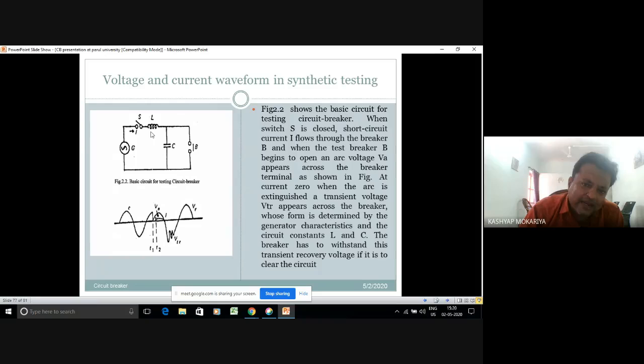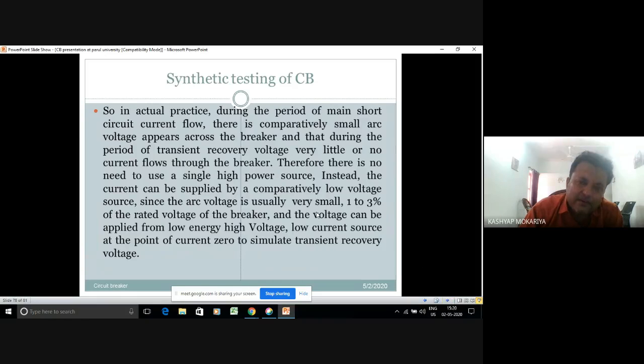Now, this is dealing with the unit level. You can see the difference here. In actual practice, during the period of main short circuit current flow, there is a comparatively small arc voltage across the breaker, and during the period of transient recovery voltage, very little or no current flows through the breaker. Therefore, there is no need to use a single high power source. Instead, the current can be supplied by a comparatively low voltage source, since the arc voltage is usually very small, 1 to 3% of the rated voltage of the breaker, and the voltage can be applied from a low energy, high voltage, low current source at the point of current zero to simulate the transient recovery voltage.